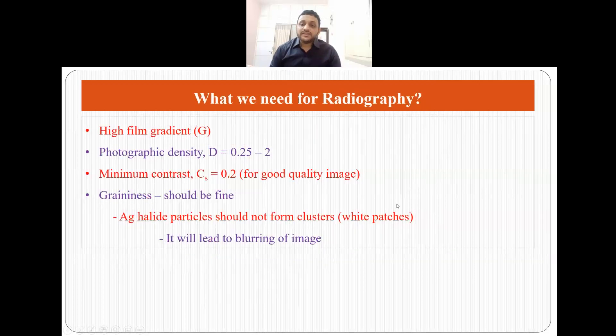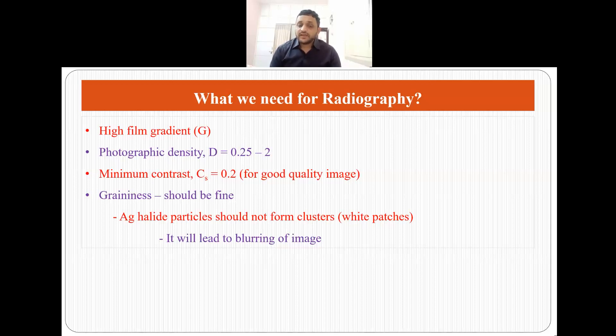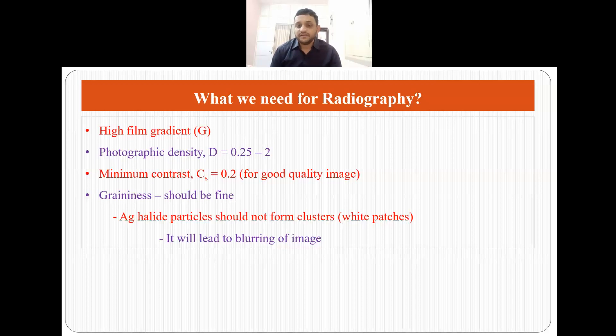For radiography, we need a high film gradient. We want photographic density to be between 0.25 and 2, contrast to be 0.2 or more, and graininess to be fine. Graininess means the silver halide particles present in the radiographic film should not form clusters or white patches, because clustering leads to blurring of the image. These are the four requirements to achieve optimum results in radiography.